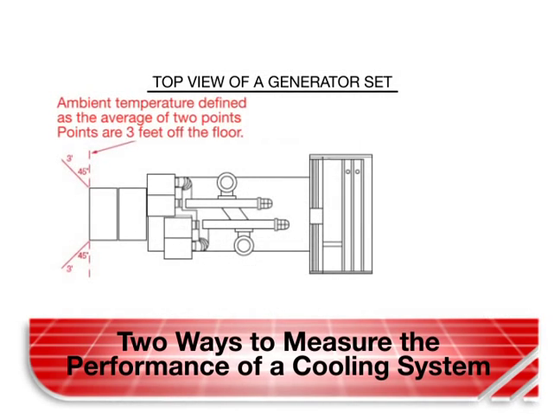When a cooling system is rated for ambient temperatures, what is measured is the temperature of air on the inlet side of the system before it picks up heat from the alternator and the engine components. This temperature is typically measured as an average of two points, as shown in the diagram. In the case of enclosed generator sets, the temperature is typically measured at the air inlet louver.